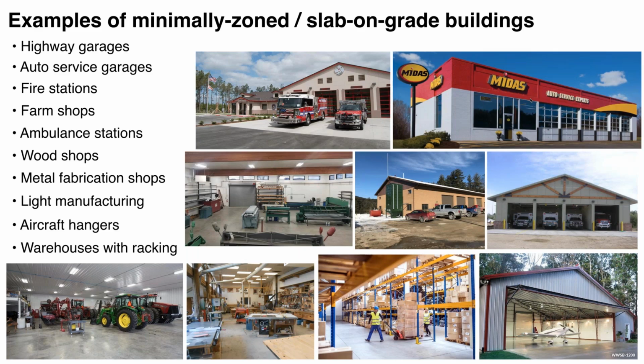...where a slab-on-grade floor is a given. And of course, that sets the stage for floor heating. And then, traditionally, in years past, these would have boilers as heat sources. So with the push towards electrification and decarbonization, we started looking at how we can take this niche of buildings and move them over to heat pumps.